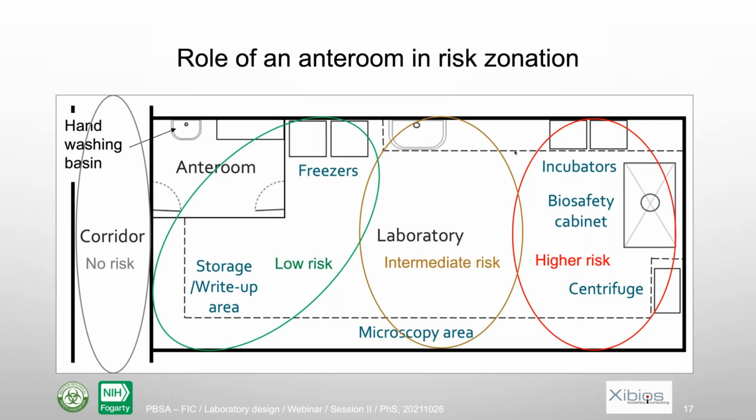Also, an anteroom helps with respect to risk zonation. So you have the lab here with the high risk area, and the low risk area close to the entrance, and you have that anteroom, which is a buffer zone there. So it's clearly a neat separation between even the low risk area and the corridor.